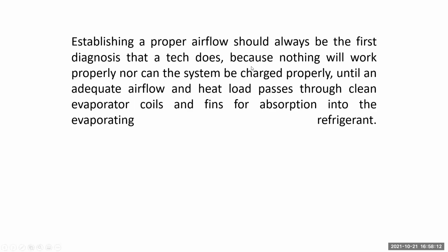Establishing a proper airflow should always be the first diagnosis that a tech does, because nothing will work properly, nor can the system be charged properly until an adequate airflow and heat load passes through a clean evaporator and fins for absorption into the evaporating refrigerant. Again, clean is the key word.